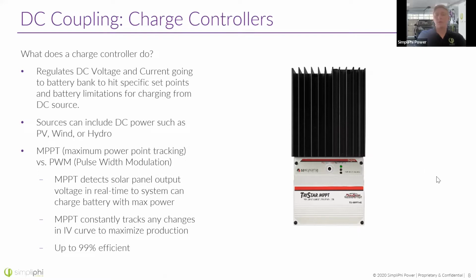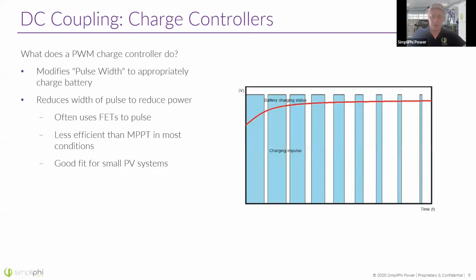Now, the other type of controller called PWM, that stands for pulse width modulation. Pulse width modulation means that the charging power of the charge controller is simply going to flicker on and off very quickly for these micro bursts. And it's going to use FETs, which is basically a switch that can switch on and off very, very fast to turn on and off that power being provided to the battery. By turning it on and off very quickly, the battery is going to see the average voltage and current that it's being provided. Instead of seeing 60 volts and 0 volts, it's really just going to see the average of the voltage it's provided.